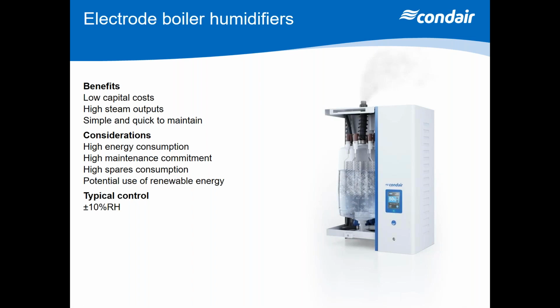Well, again, that really relies on the conductivity of the water. And to give you a couple of good site examples, a good example was a factory up in Leeds in the north of England. Water quality was pretty good. They got 350 microsiemens water quality, and they were using them 6 to 8 months of the year. And typically they would change the cylinders once a year. That's a pretty good application.